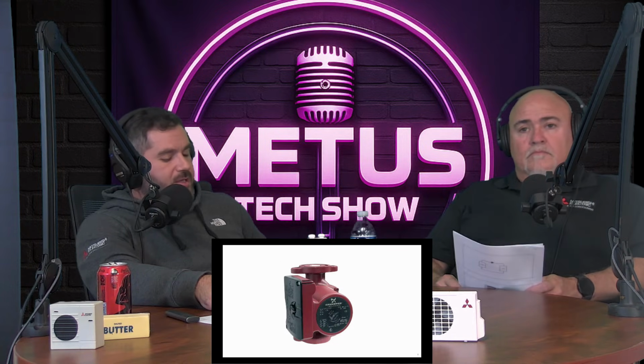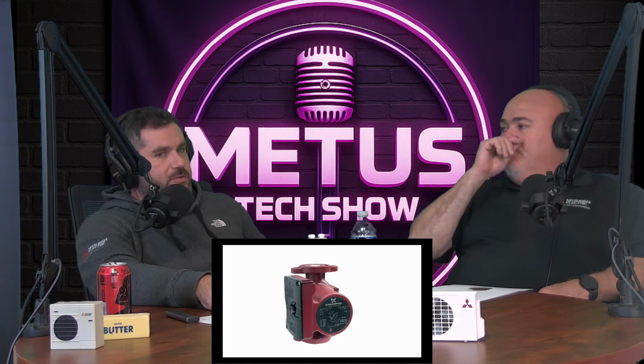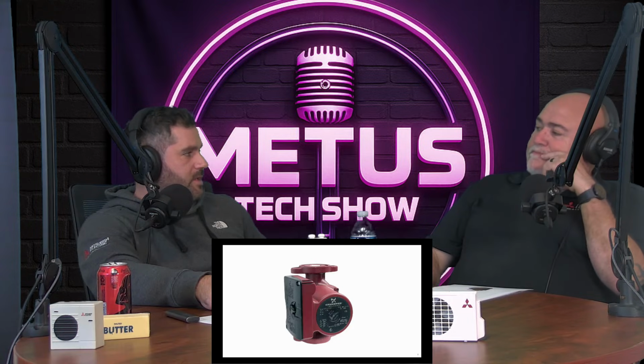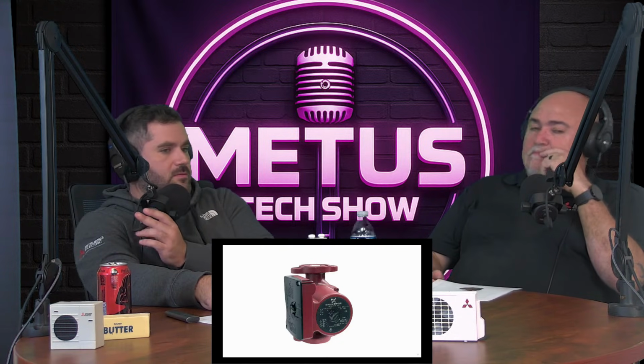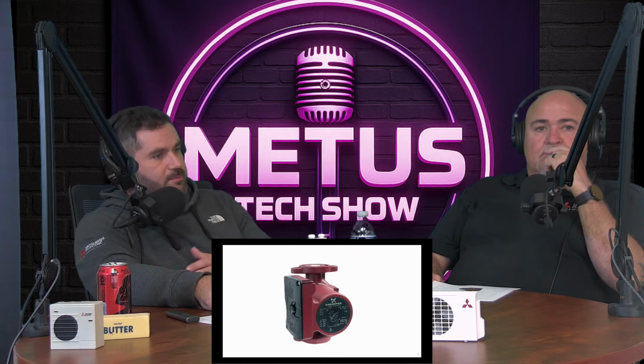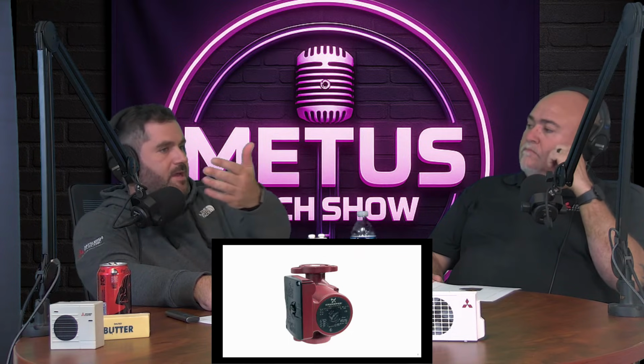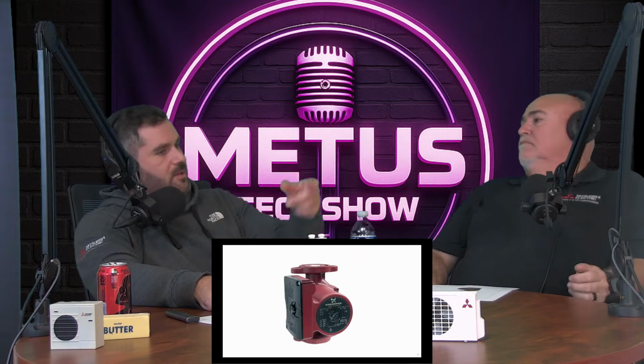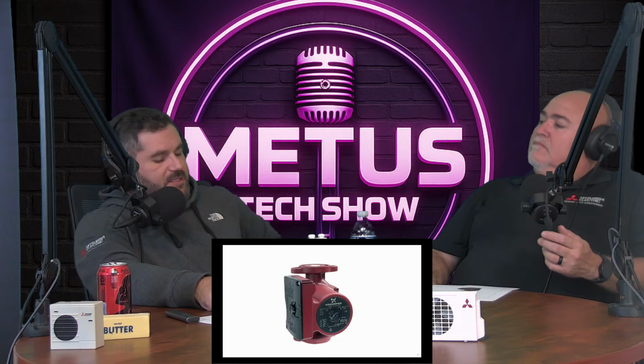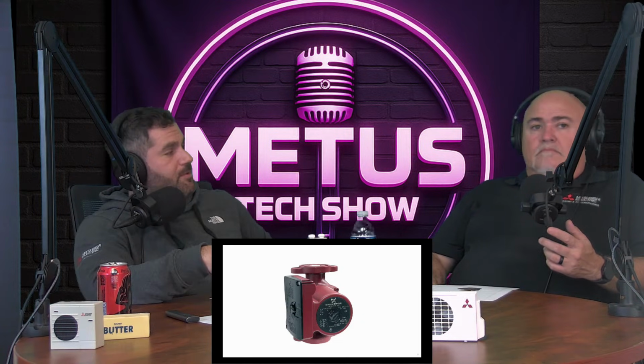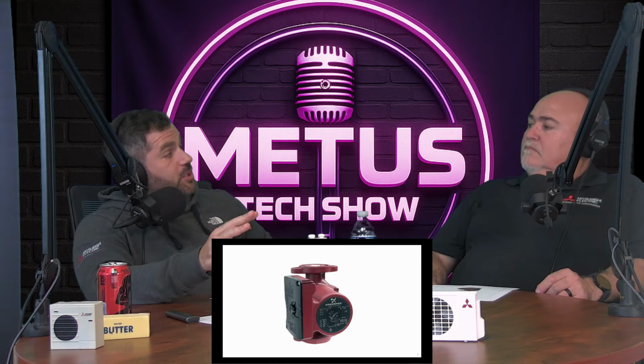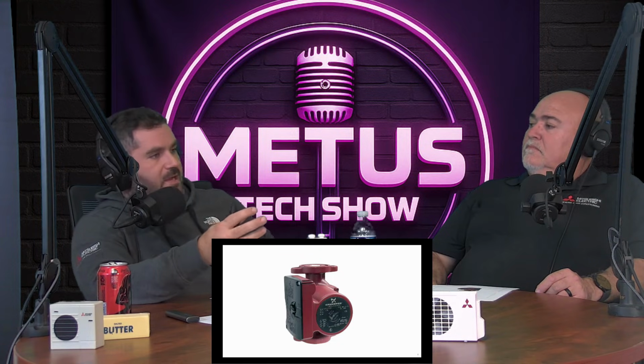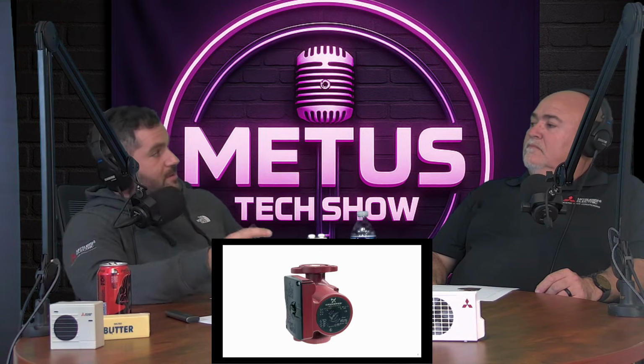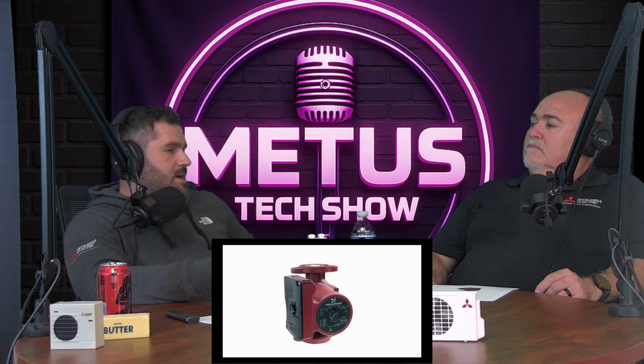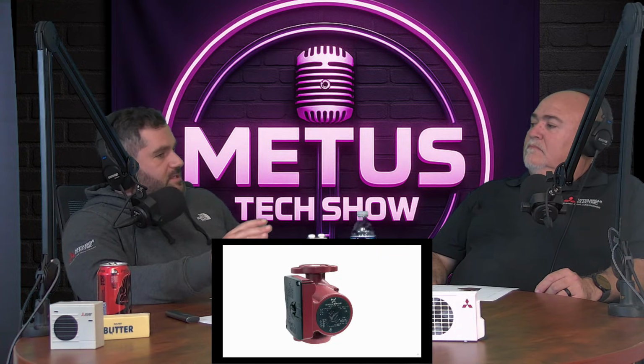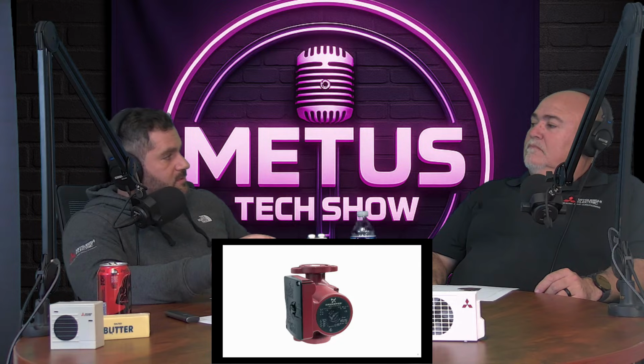But basically all these circulators are differential pressure machines. That's all they do. They create differential pressure. What they're trying to do is build pressure on the head side, and that creates a suction pressure, and that's what allows the water to flow. A lot of people think these are really pushing or pulling water, and so there's a lot of discrepancy on where to put this. Should I put it on the supply? Does it go on the return? In the grand scheme of things, there are some things to consider as far as where you put it.